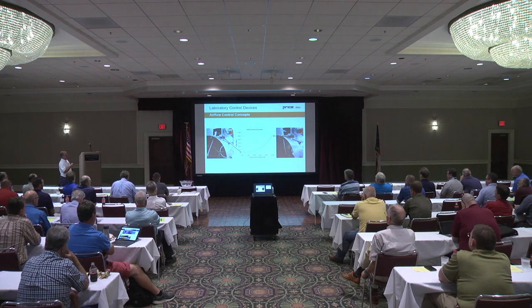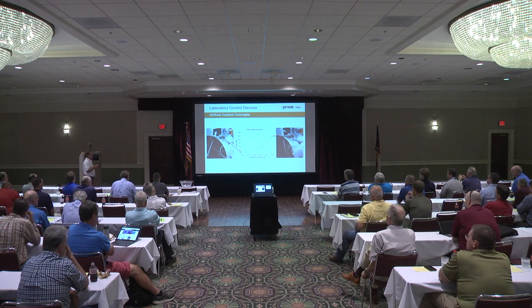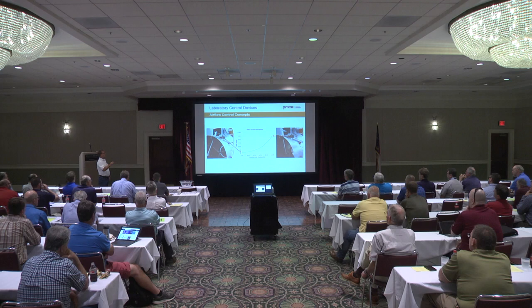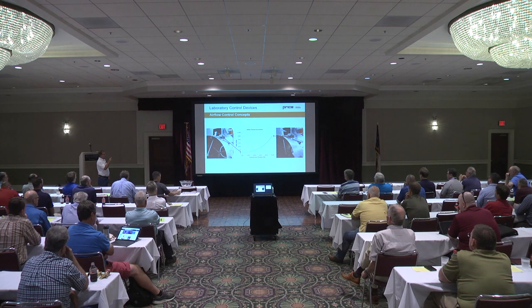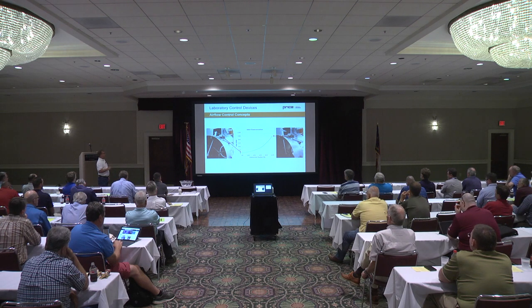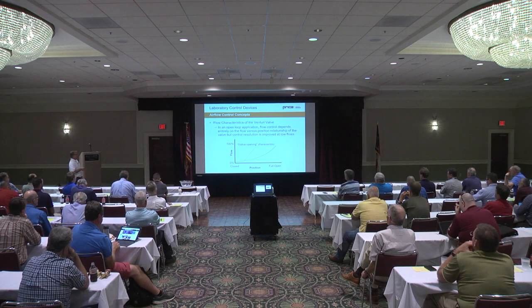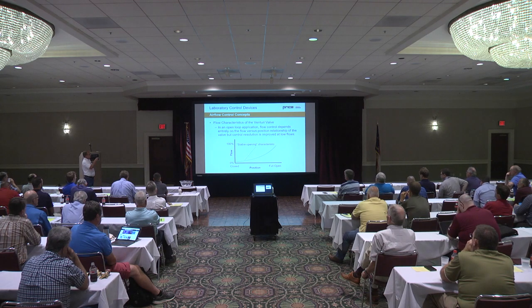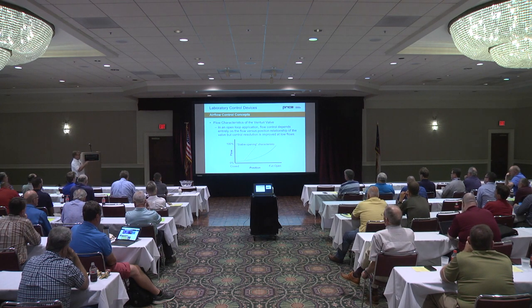So the flow characteristic of this type of device is what I'll refer to commonly as low and slow. The CFM will start out low, and it'll increase parabolically as you move from 0 to 100%. So the large percentage of your flow doesn't occur at the start point, but as you further stroke the valve towards its full open position. So you get a nice smooth airflow change throughout the full travel of the valve or the shaft on the actuator. Again, this is just another representation of that concept. With open loop application driving the position of the valve, the flow is nice and stable as you move from full close to full open.